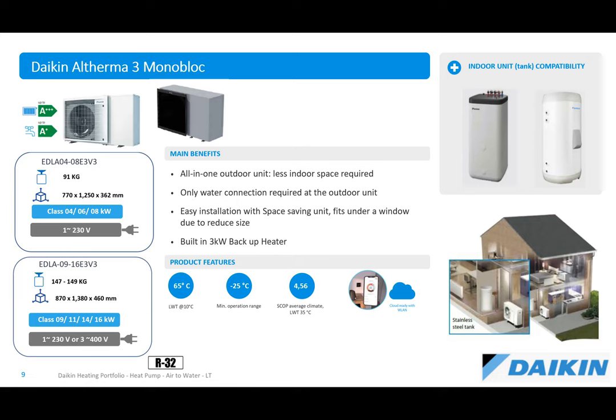So the benefits of your monoblock: you're not taking up any space inside. All you have inside really is your hot water cylinder and your hot press or your utility room. You have water-only connection between the indoor and the outdoor unit. And all of our heat pumps come with a built-in 3 kilowatt backup heater. And that's there purely as a backup. It assists when the heat pumps are initially being commissioned.